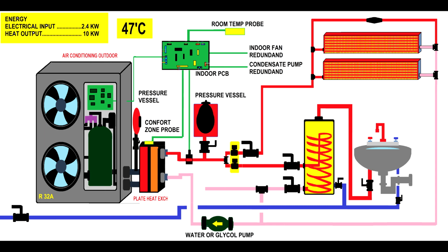And also you can have a flow switch connected to the floating switch of the water pump, and then you will convert the system that way, so you run safe. Can you imagine if you do not have, as an example, water circulation through the system, then the flow switch will keep the circuit open, and the printed circuit board will sense that, and it will instruct the outdoor not to run, because you do not want to overheat the outdoor.